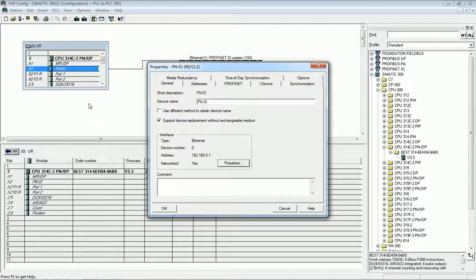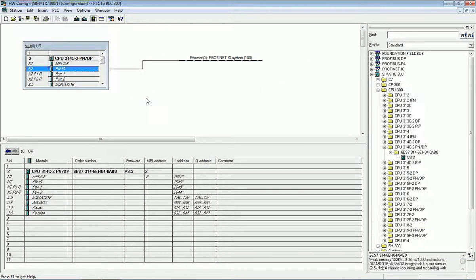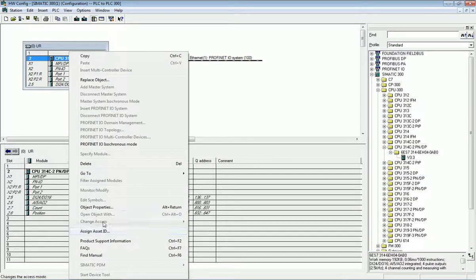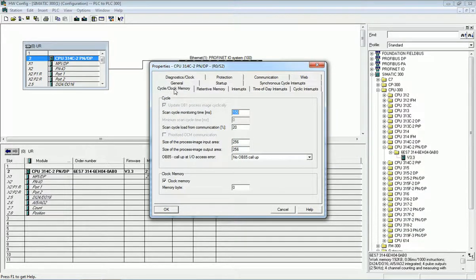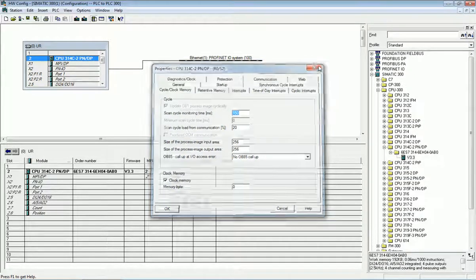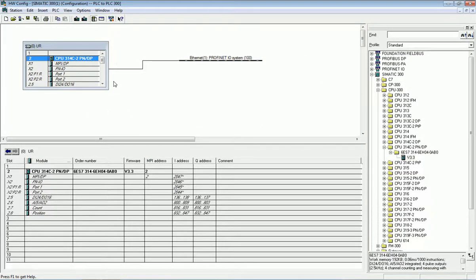The second thing we need to do for PLC-to-PLC communication is to enable the memory bit, also called clock memory. To enable clock memory, we open the CPU properties by right-clicking and going to Object Properties. Here we get the option for Cycle/Clock Memory, and from there we enable clock memory. You can set any byte address, and as per the memory bit you can set the clock pulse for synchronization.